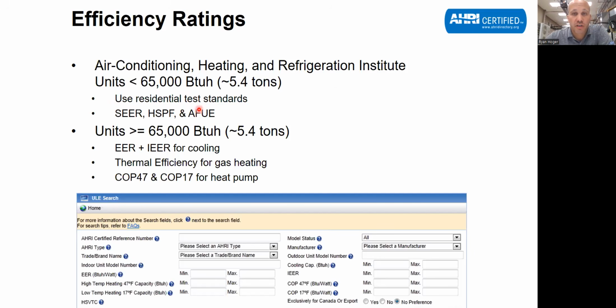So for starters, for the kinds of equipment we're talking about today, which was commercial packaged rooftops and commercial DX split systems, there's this magical dividing line of 65,000 BTUs of cooling. If it's less than 65,000 BTUs of cooling, the equipment gets tested as if it was a residential application, and they use the residential testing metrics. And if it's above 65,000, 5 tons of cooling and above, they do the commercial testing and the commercial metrics. However, residential small systems get put into commercial buildings all the time. It's a daily thing. It's constantly happening, right?